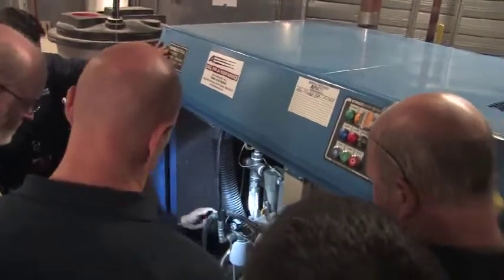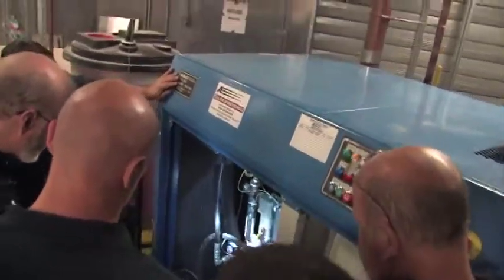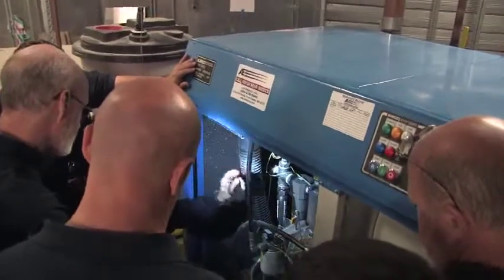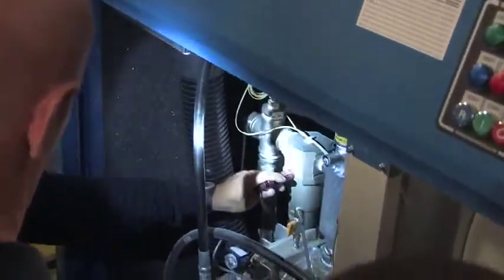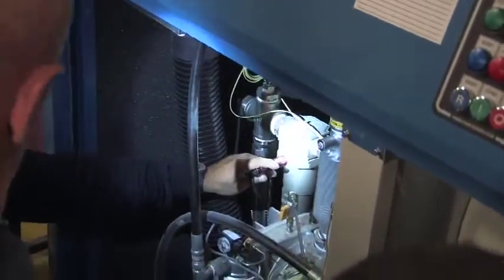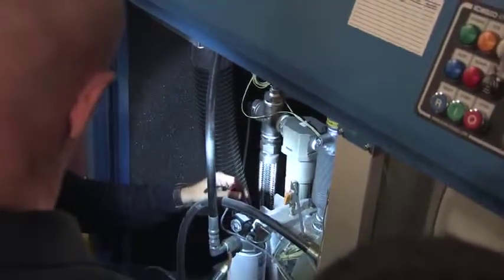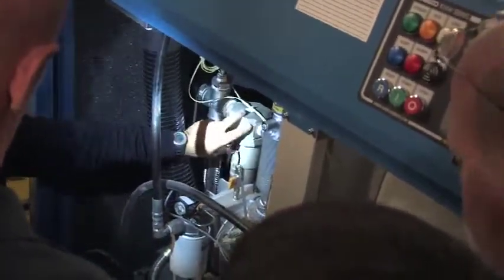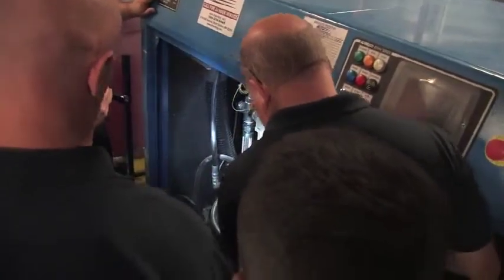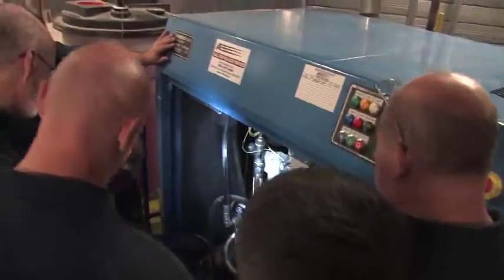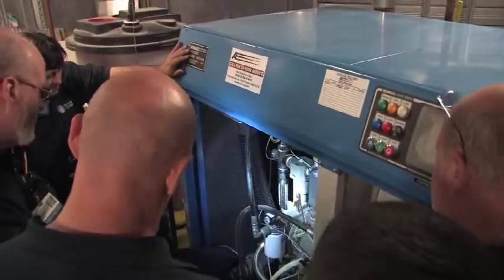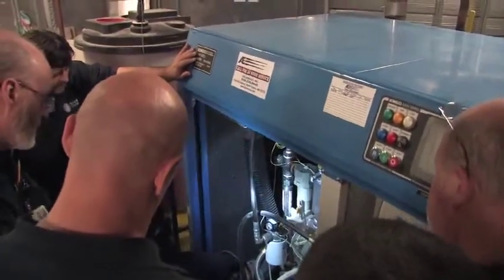Exactly. Your most critical thing here is actually your intake filter, and the second most critical thing is the condensate separator. The inlet filter keeps particulates from getting in there, and the condensate filter keeps liquid water from hitting the second stage, which is really hot. When you've got a screw that's running at 400 plus degrees and water hits it, the water explodes into steam.